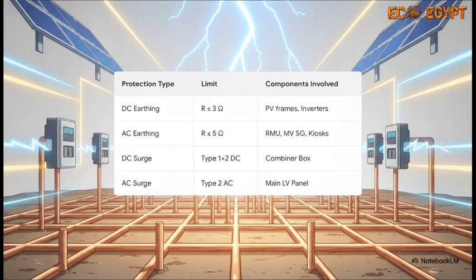The answer is a meticulously engineered, low-impedance path to ground. The entire site is bonded together into this massive main earth loop using copper-bonded steel rods and copper tape, buried right in the earth. The engineering standard here is strict. You have to keep the DC resistance under 3 ohms and the AC resistance across the MV switchgear and RMUs under 5 ohms. Plus, this grounding grid doesn't work alone. It's paired with strategic surge protection devices, or SPDs. Type 1 and Type 2 SPDs are placed at critical junctions, like the string combiner boxes and main LV distribution panels, to instantly shunt any of those lightning transients safely into the dirt before they can fry the equipment.